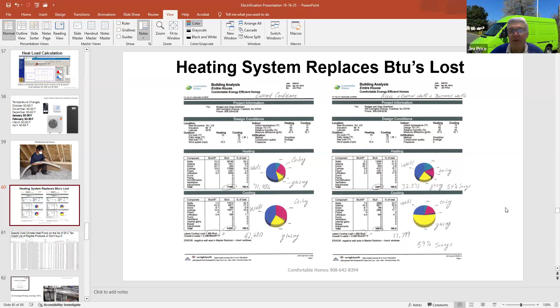So at 5 degrees outside, we're going to have these capacities. If we have something close to 32,000 BTUs on this page — and I took a random page, I didn't look specifically for 32,000 BTUs — then it would tell us what we need for this equipment, and we'd put that equipment into that house. So that's how we size it.